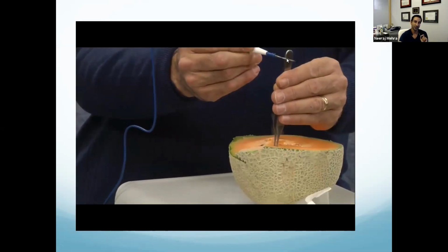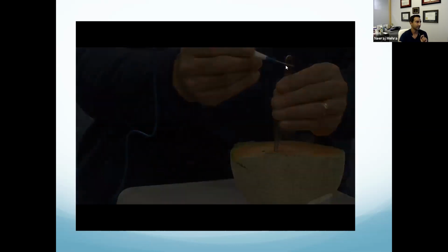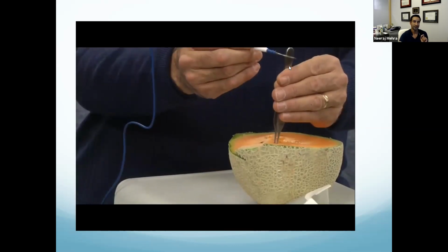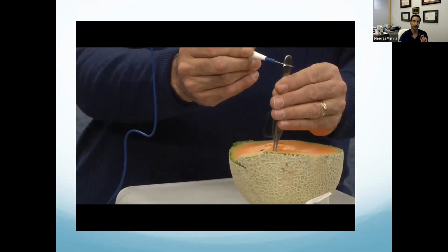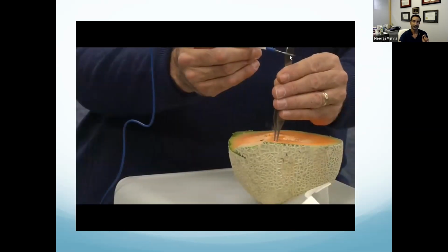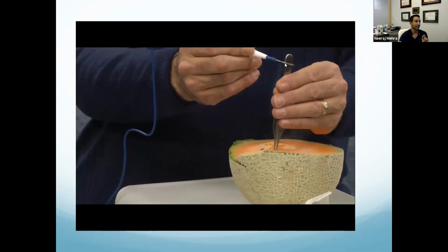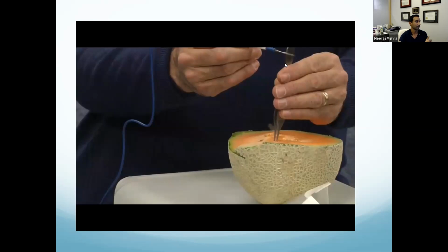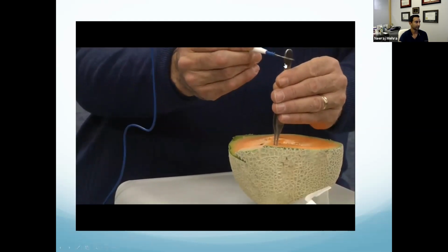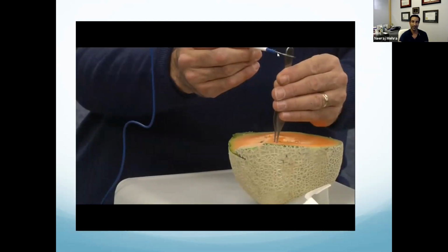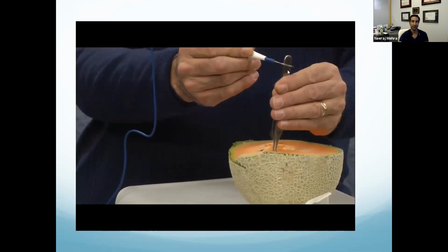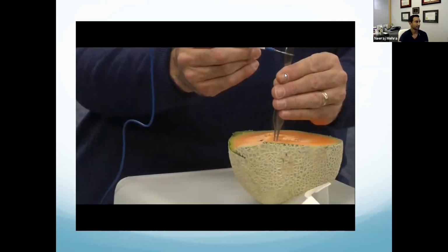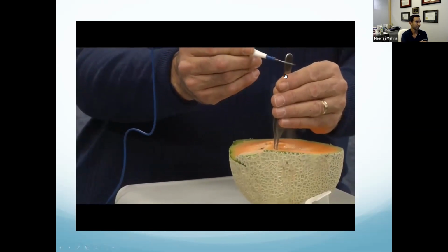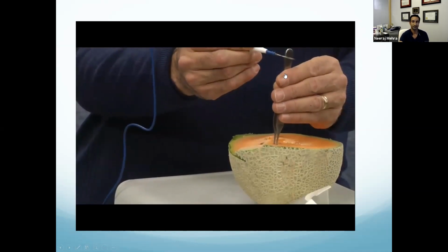Do you see how he's touching the forceps with the side of it? That's an area of high current density, and you can get sparks there as well, because he's touching edge to edge. If there's any separation, you're going to create a spark, and a spark will be a high voltage, and that'll create a zap. So the safe thing to do is to use the flat part of your bovie with the flat part of your forceps. Flat against flat gives you high surface area, and high surface area is low current density, so you're less likely to create a zap.